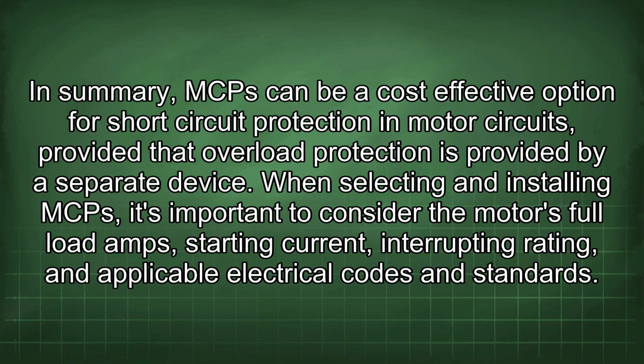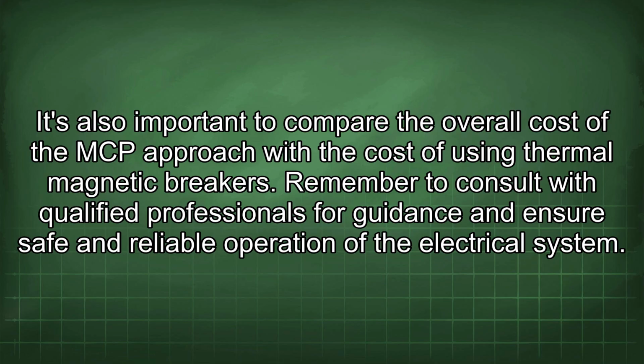In summary, MCP can be a cost-effective option for short-circuit protection in motor circuits, provided that overload protection is provided by a separate device. When selecting and installing MCP, it's important to consider the motor's full load amps, starting current, interrupting rating, and applicable electrical codes and standards. It's also important to compare the overall cost of the MCP approach with the cost of using thermal magnetic breakers. Remember to consult with qualified professionals for guidance and ensure safe and reliable operation of the electrical system.